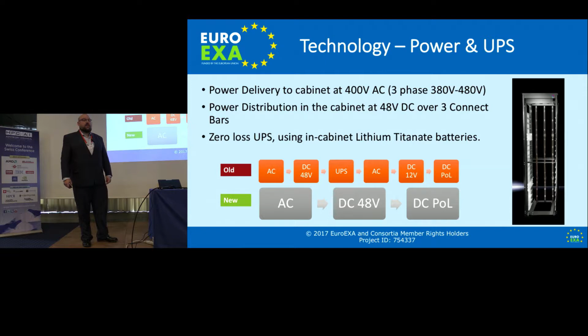So, batteries. Now, when it comes to batteries normally, if you've got a UPS, it's holding you up for at least 10 minutes. Even if you didn't design it to hold you up for 10 minutes, guess what—it's holding you up for 10 minutes. That's because it was designed around the battery chemistry, which can't discharge faster than 10 minutes.